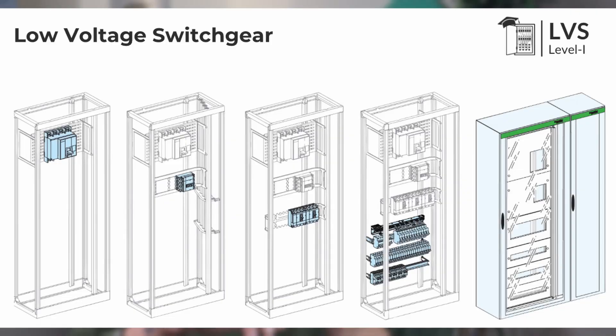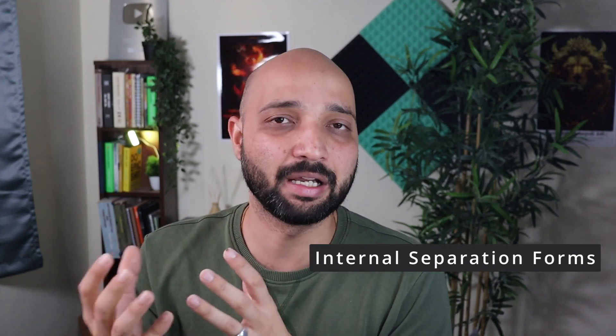There are different components used in low voltage switchgear — air circuit breakers, MCBs, MCCBs, and busbars running through the switchgear. With the help of physical barriers, such as insulating or plastic material, we separate each compartment — the busbars, circuit breakers, and MCBs. Those barriers are the internal separation forms, and their technical standard name is internal separation forms.